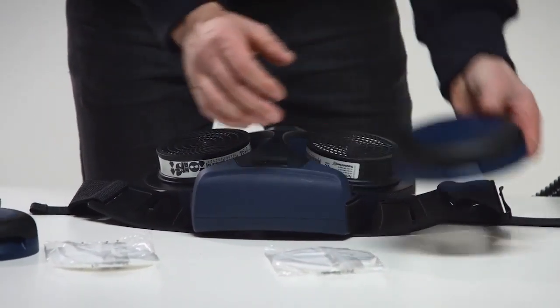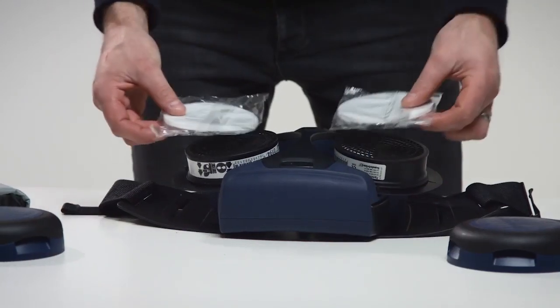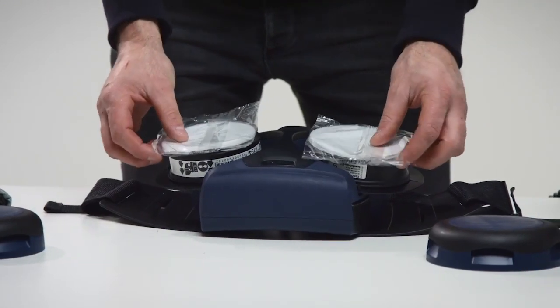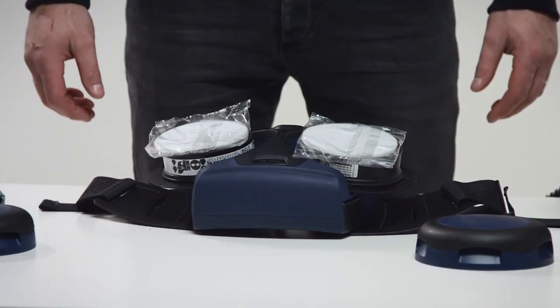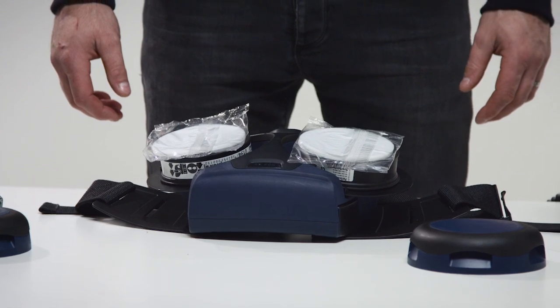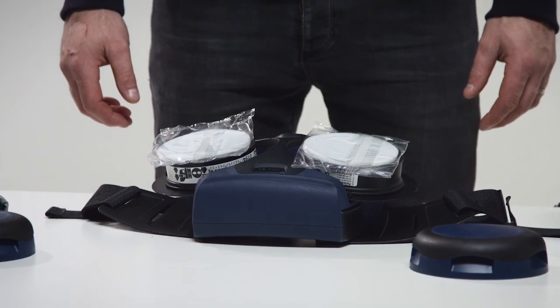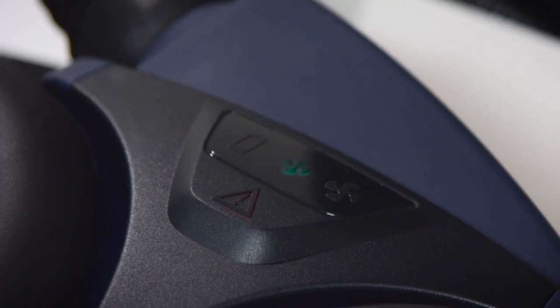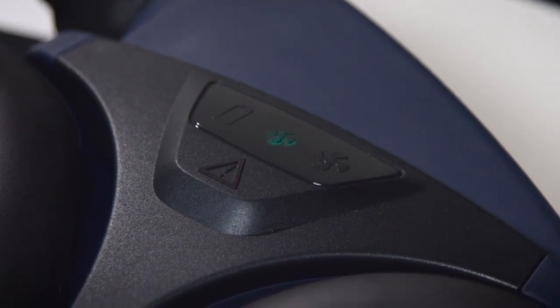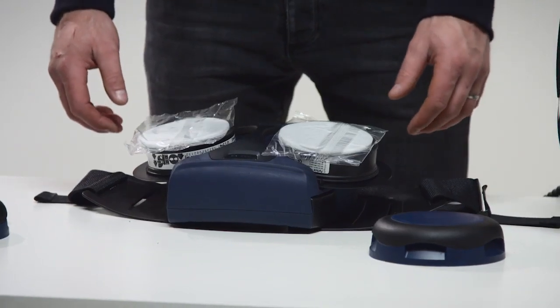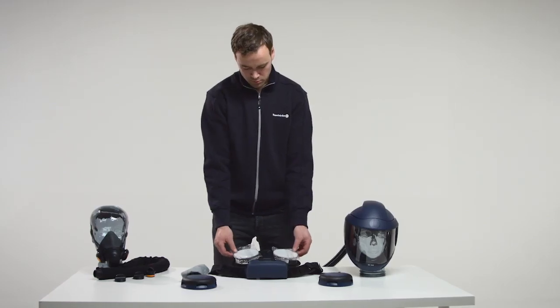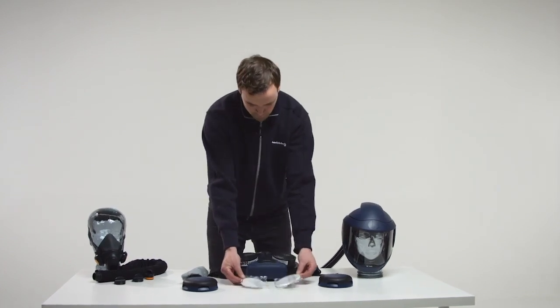If the particle filters are clogged, a continuous sound signal will be heard for 5 seconds. The built-in vibrator will be activated for 5 seconds. The red warning triangle in the display will flash. Action: Immediately interrupt the work, leave the area and change the filter.